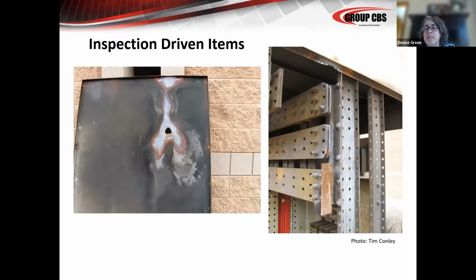So this is an interesting situation that was definitely a maintenance inspection driven arc fault. If you can see, those 3 horizontal bars are the bus, the line bus that goes through the gear. And upon initial installation, there was supposed to be a piece of insulation on the end of each bus bar. Well, for whatever reason, phase A and phase B did not have that insulation installed.